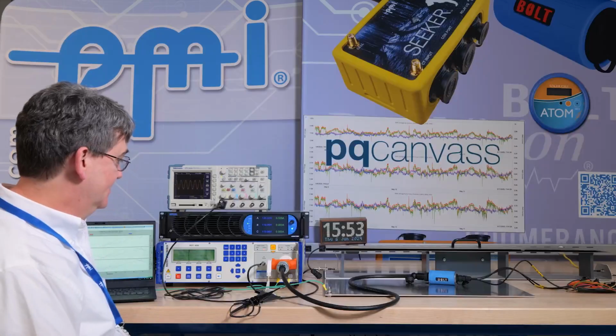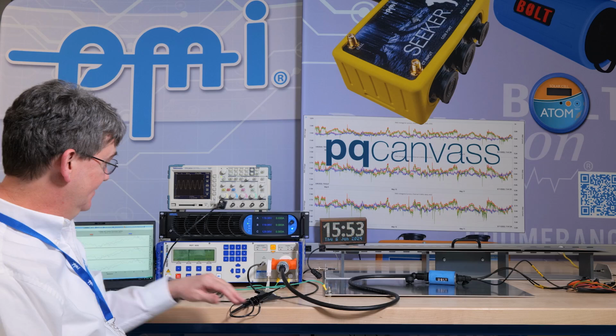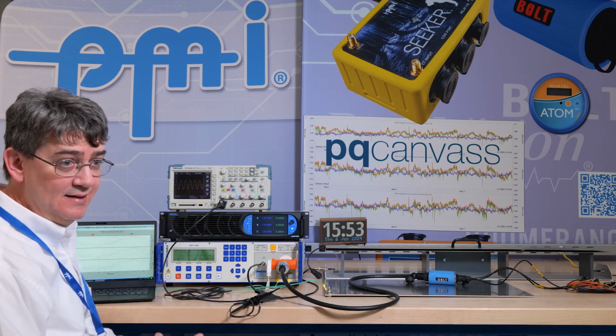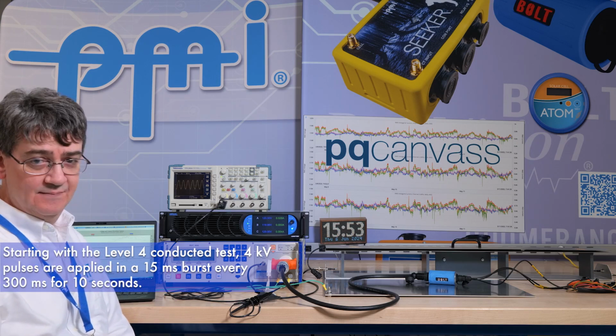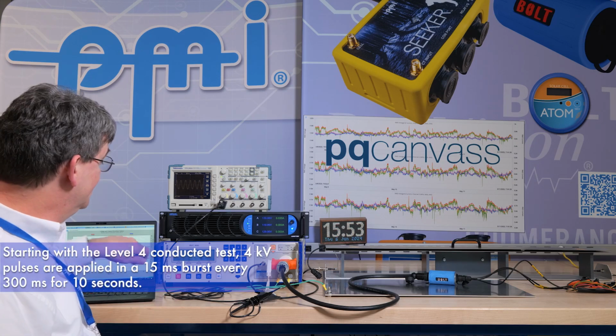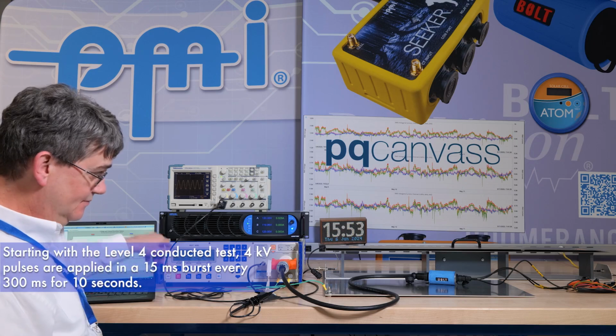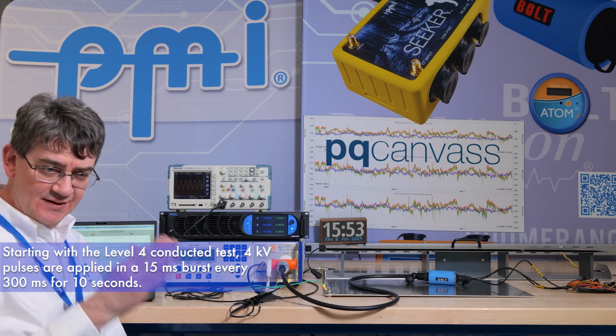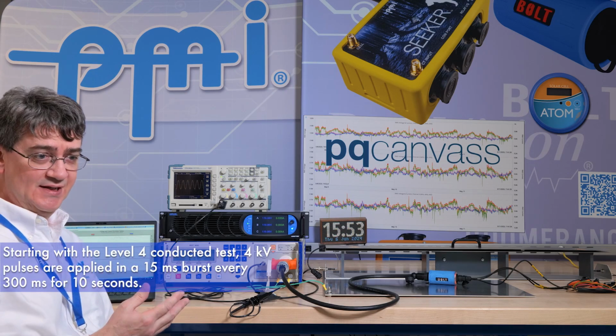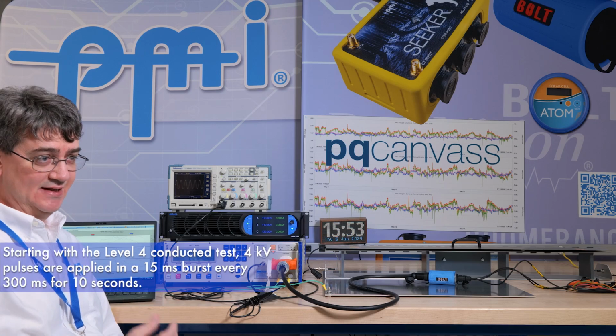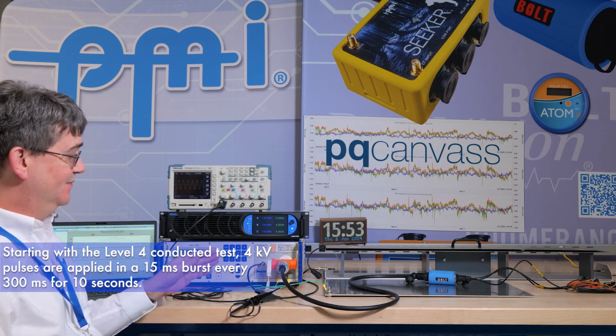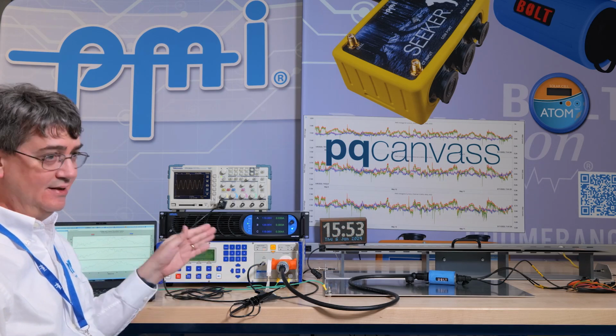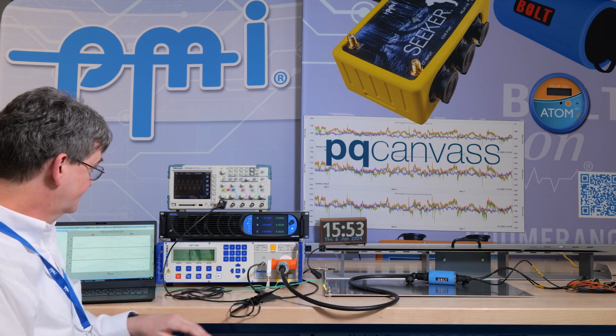So we're going to start with the conductive version. This piece of test equipment can apply these pulses, and we're going with the most harsh standard, which is level 4. And with level 4 testing, the machine applies 4 kV pulses in a 5 kilohertz rate for 15 milliseconds, and it repeats this every 300 milliseconds for 10 seconds. And it does this both line to ground and neutral to ground on a power cord.